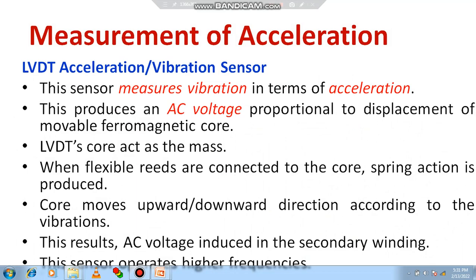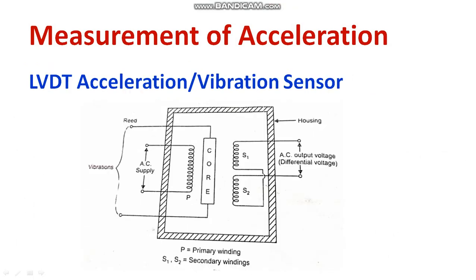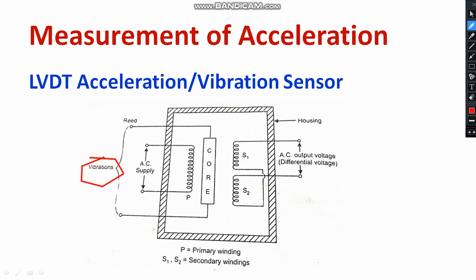Another method is the LVDT acceleration sensor. We already discussed the linear variable differential transducer — it basically operates based on the movement of the core. The core is directly connected to the mechanical object where vibration is produced. We have a primary winding and two secondary windings in series and opposite configuration. With respect to changes in the core position, the output voltage changes.